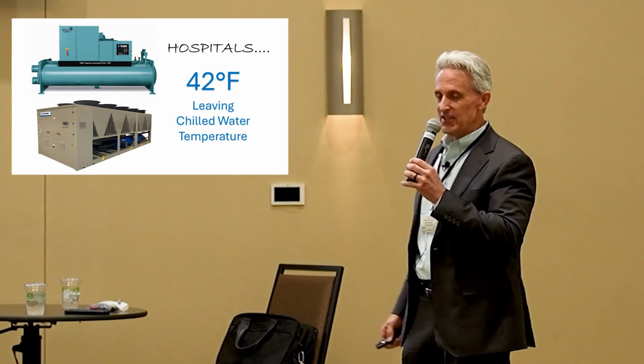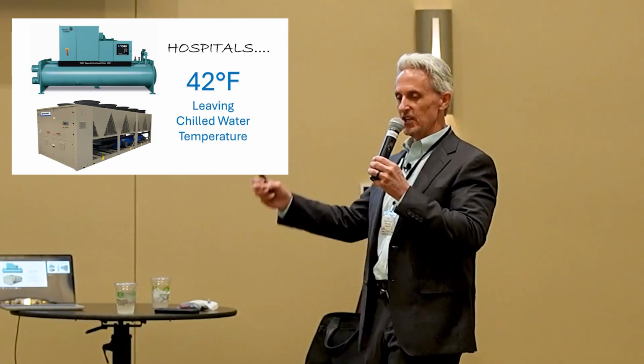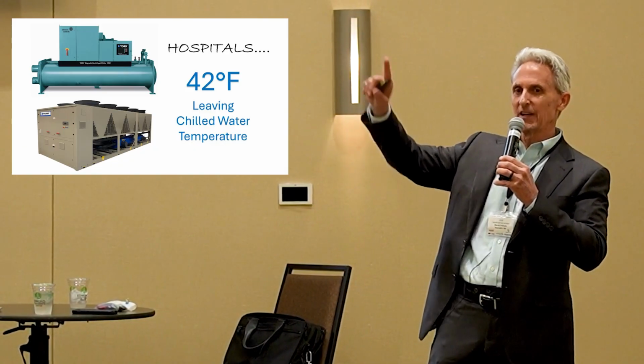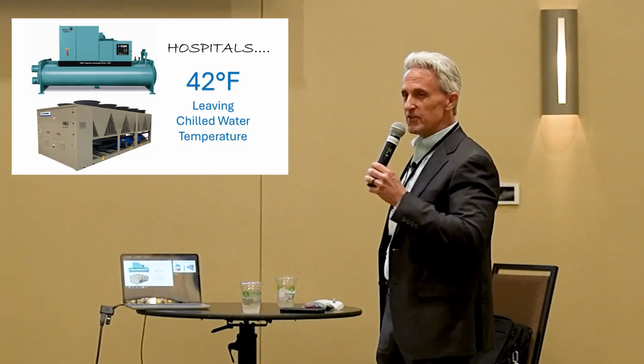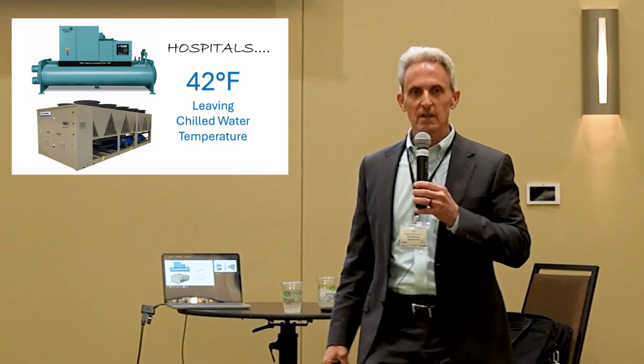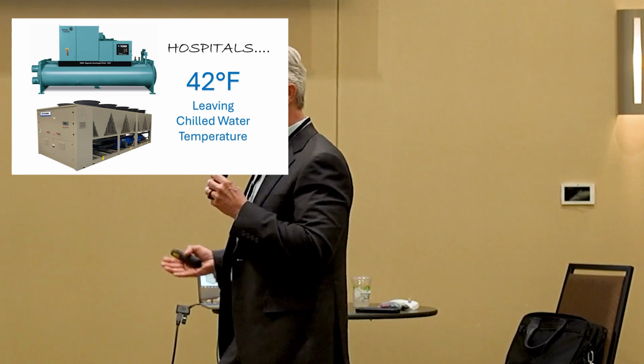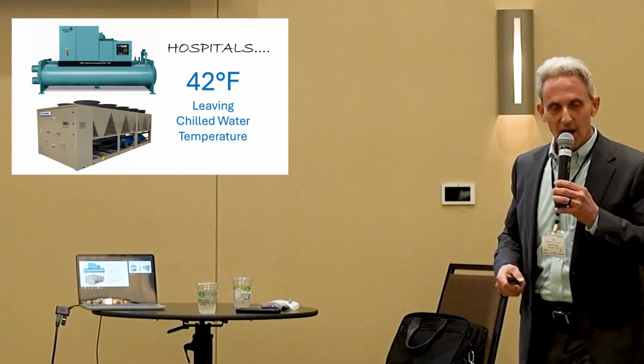The national average, based on what ASHE tells us, ASHE is the American Society for Healthcare Engineering, the average in the United States of America is 42 degrees Fahrenheit chilled water temperature leaving the central plant. That means it's probably a little warmer by the time it gets to the coil, okay? Why are we designing hospitals at 42 degree Fahrenheit leaving chilled water temperature? You know the answer. Because that's the way we've always done it. That's the only answer I can figure out, right? And why we put hospital operating rooms on the same loop with the rest of the hospital befuddles me. I don't know why, because it doesn't work.